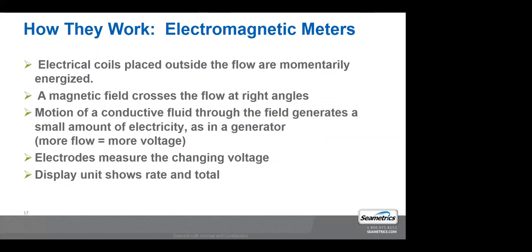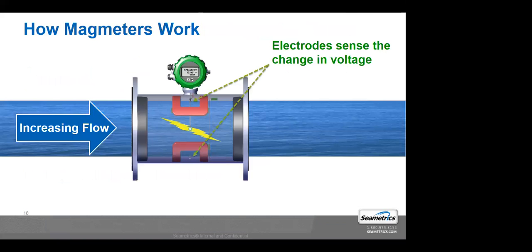That's what they're measuring. There's electrodes inside the meter, and I welcome any of you to walk up and look at the meter if you'd like to see what they look like, little stainless steel buttons in the meter. And those electrodes are measuring the change in voltage as the fluid's flowing through it. And then you end up getting your rate and total, comes out on the screen. This kind of shows you what's going on inside the pipe.